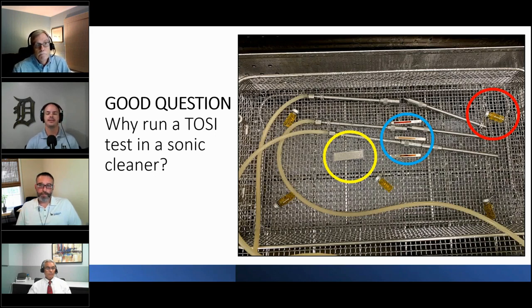So in this picture, you see in that yellow circle, a TOSI test, right? This came back completely clean after the cycle was ran. So we know that the ultrasonic was able to clean a clinically relevant test soil from a stainless steel instrument. You can see in the red circle, going back to that cavitation, right? We want to make sure that there's ultrasonic energy going through our bath. That is a Sonocheck test in that red circle. This is a vial that starts out green in color, and in the presence of cavitation or ultrasonic energy, it will turn yellow.